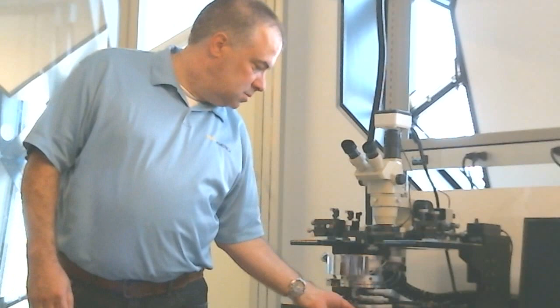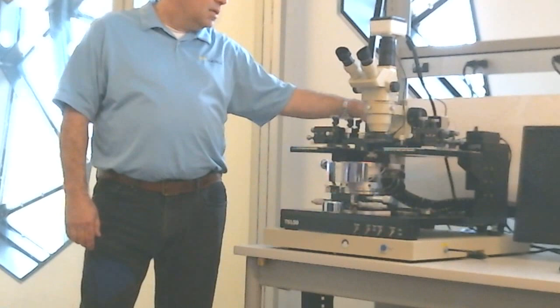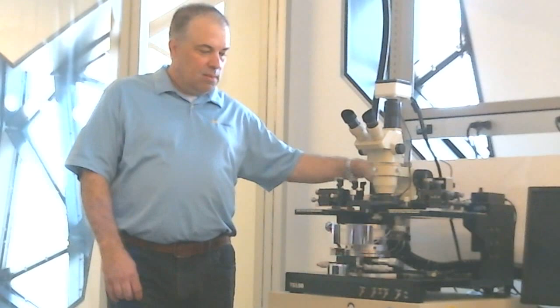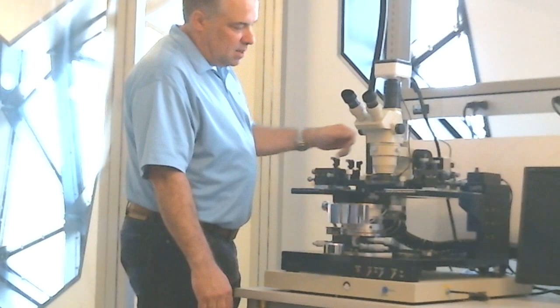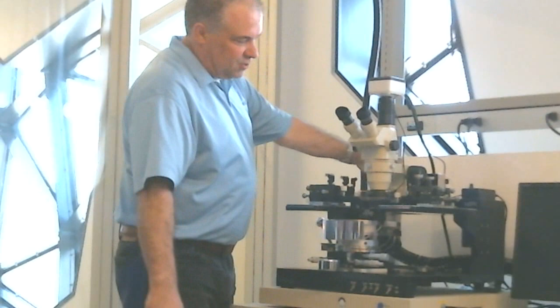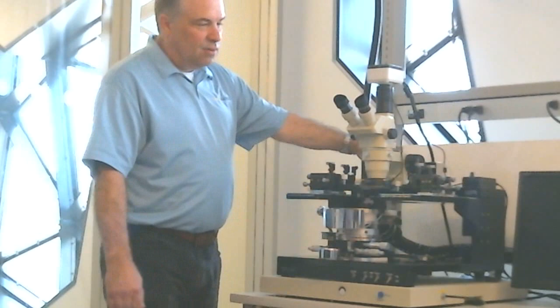And there's also an XY movement as well. It's not a lead screw, it works on an air bearing, and there's a handle on the left side. You probably can't see it, but if you flip the scope switch down here, it'll enable this air bearing, and when you have the microscope where you want it, you flip the microscope switch back up. Because I have the vacuum pump off, that's not going to lock. I want to turn that back off, but just for demonstration purposes, now it's locked. Turn that off, and it'll float around. And it'll lock back in place once you have the microscope in place. I'm just going to shut off the vacuum pump for now, just because it makes a little bit of noise.